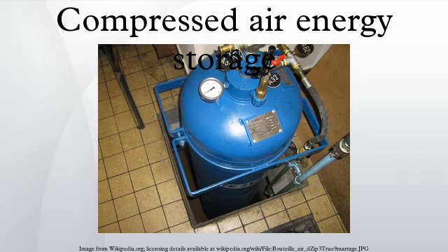This reheating can be accomplished with a natural gas-fired burner for utility-grade storage or with a heated metal mass. As recovery is often most needed when renewable sources are quiescent, fuel must be burned to make up for the wasted heat. This degrades the efficiency of the storage recovery cycle. And while this approach is relatively simple, the burning of fuel adds to the cost of the recovered electrical energy and compromises the ecological benefits associated with most renewable energy sources. Nevertheless, this is thus far the only system which has been implemented commercially.